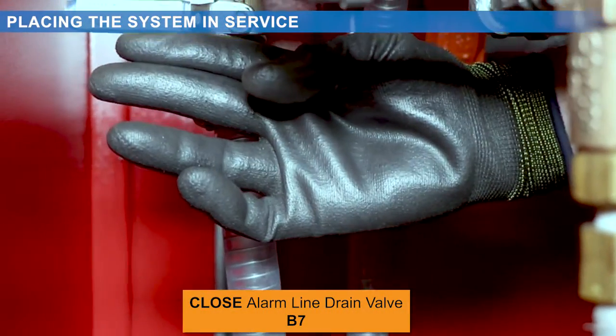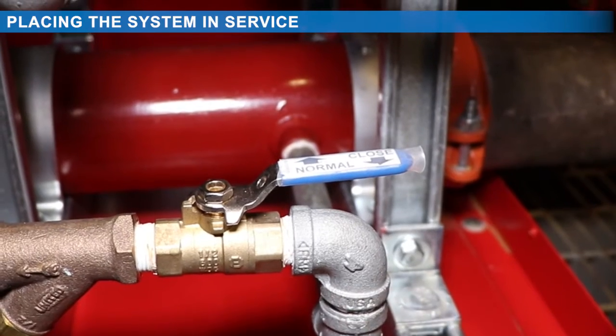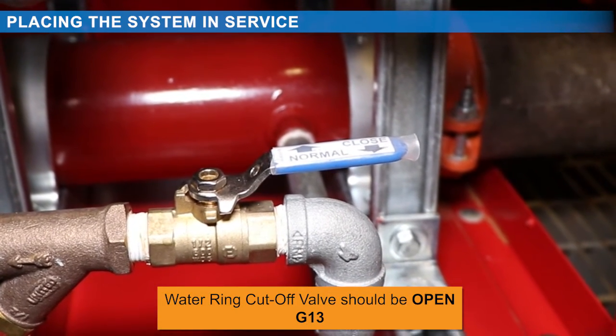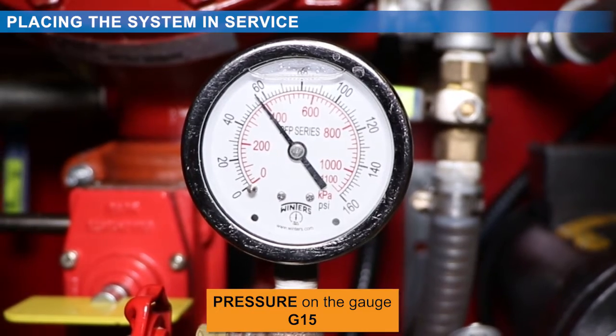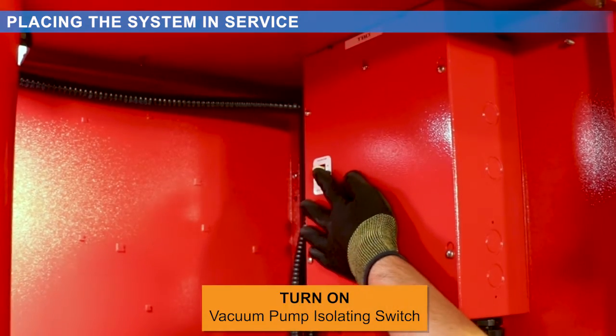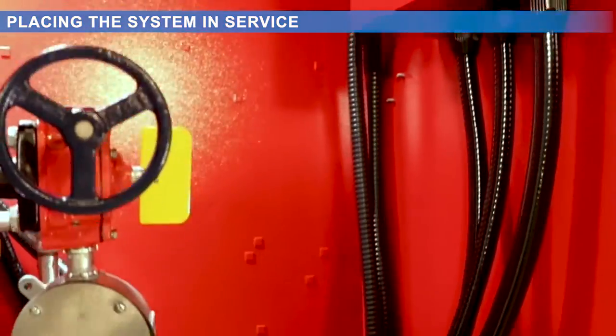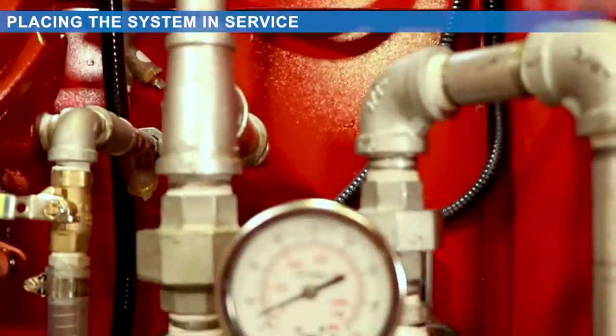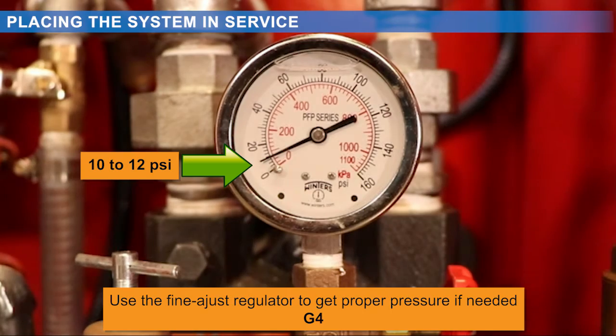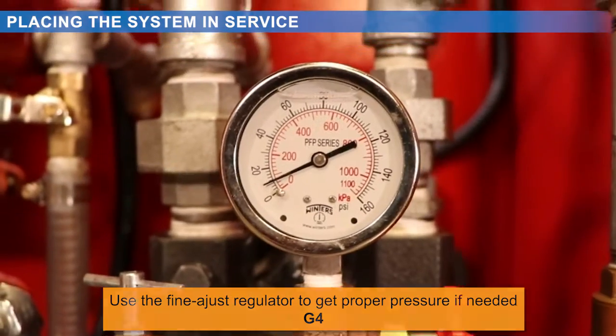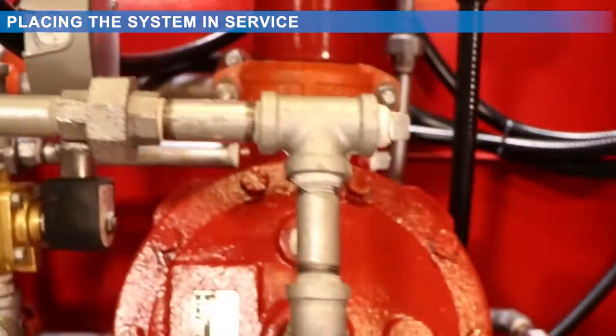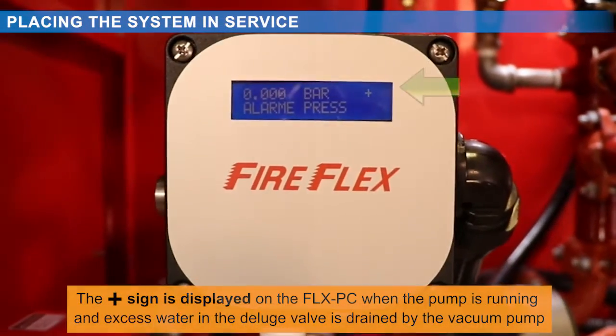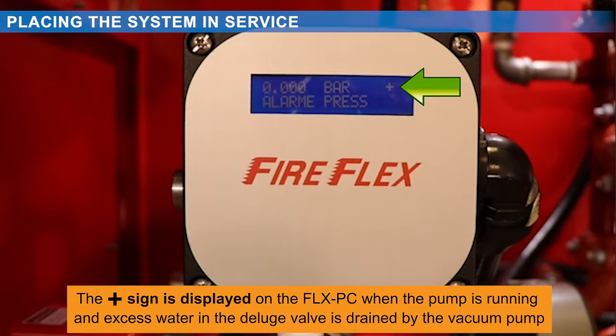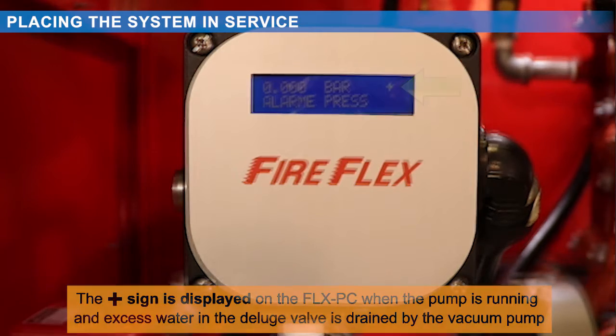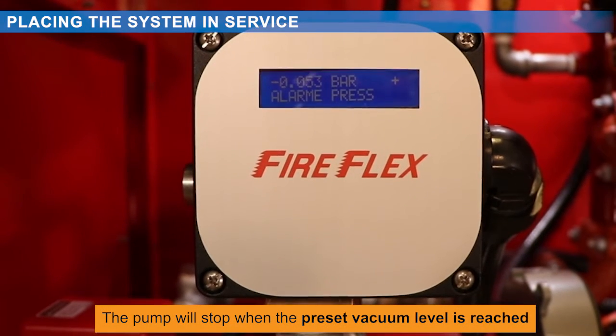The vacuum pump requires water pressure for it to create vacuum. Be sure the water ring cutoff valve is open and there is pressure on the gauge. Turn on the vacuum pump isolating switch. Gauge must show water pressure between 10 to 12 psi. This sign will be displayed on the FLX PC when the pump is running and excess water in the deluge valve will be drained by the vacuum pump. The pump will stop when the preset vacuum level is reached.